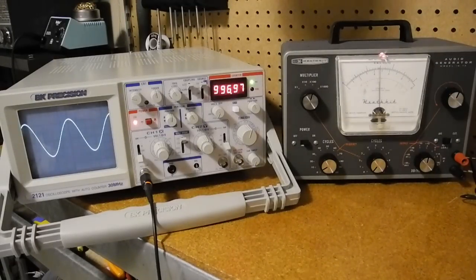The meter is calibrated, so it's reasonably accurate. In order for the output level displayed on the meter to be accurate, either the internal 600 ohm load needs to be turned on or the unit needs to be terminated in a 600 ohm load.